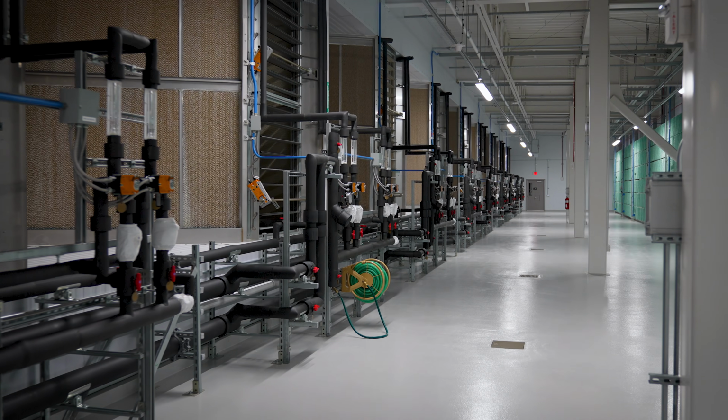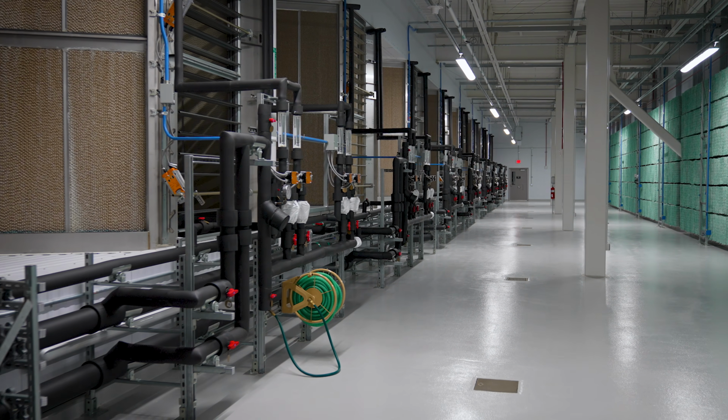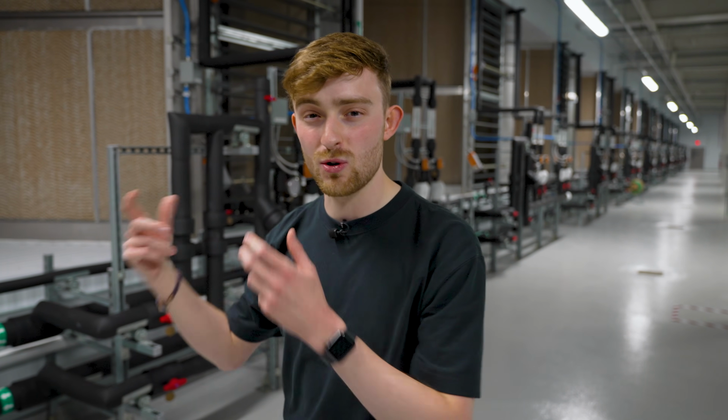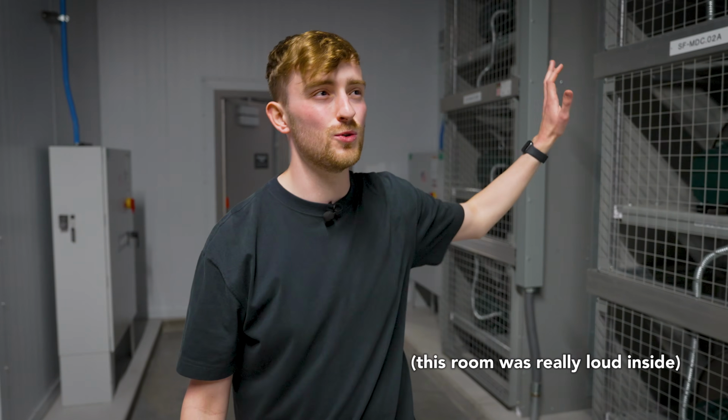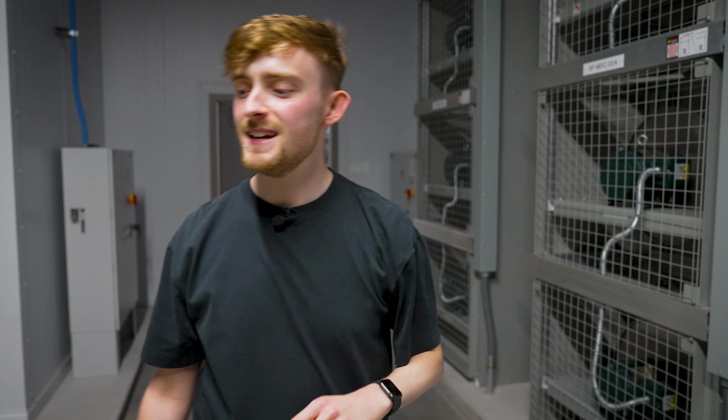For a little bit more context as to why this method is being used, this entire data center is air cooled. So liquid is not actually being ran through the server racks, it is purely being cooled by air. So the use of liquid in this data center is here to actually just cool the air down a little bit.